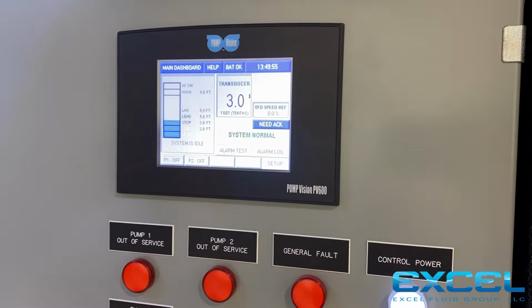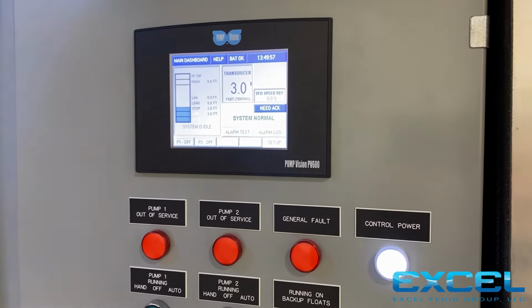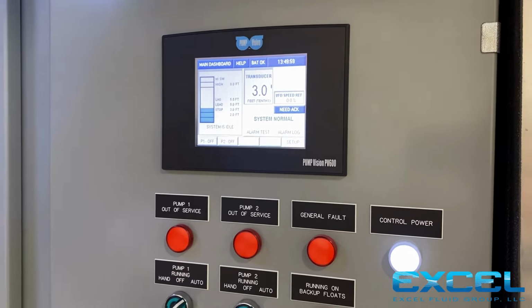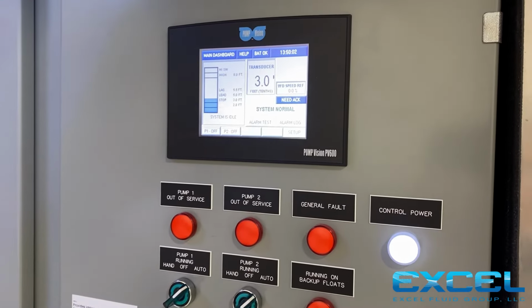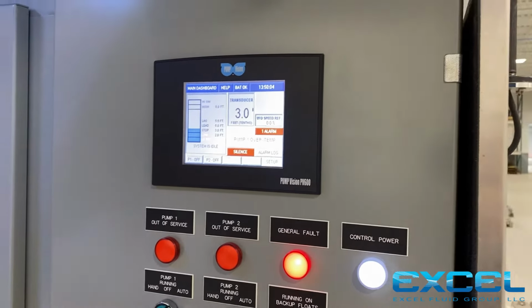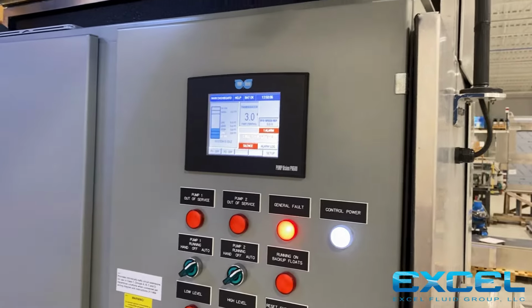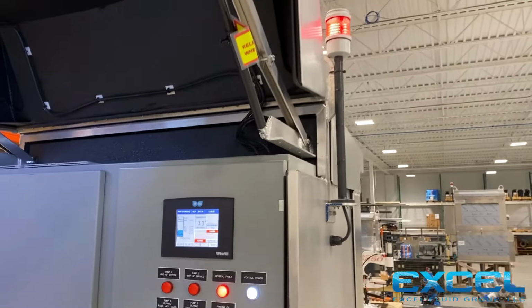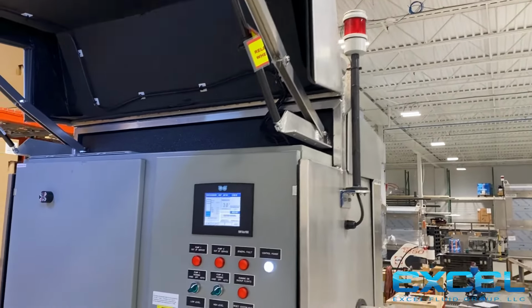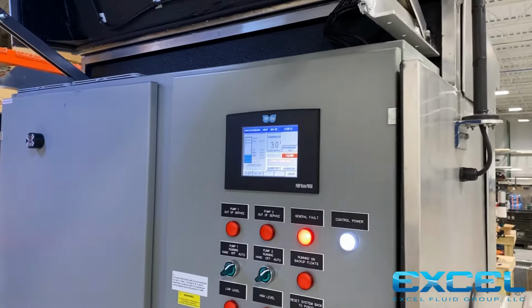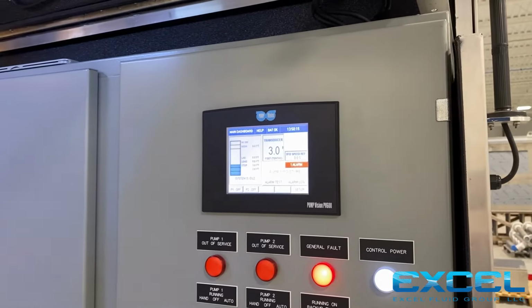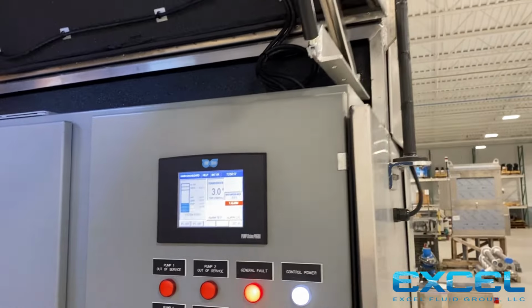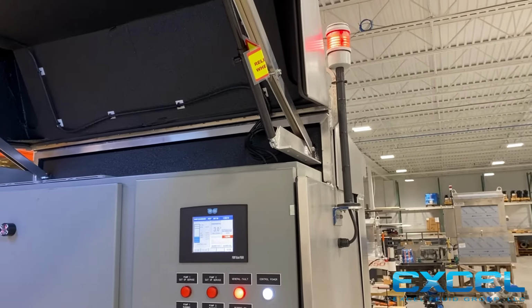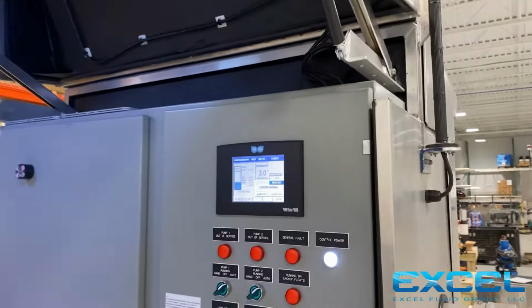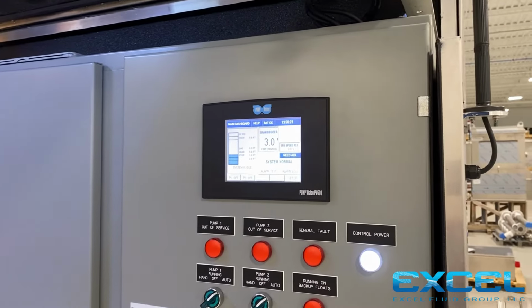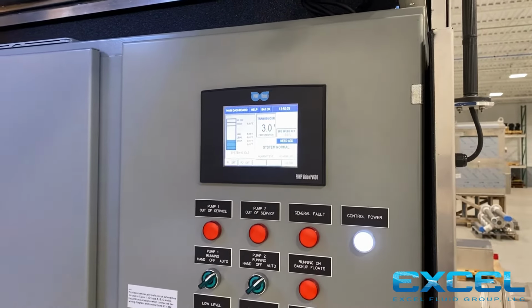If it's hooked up to telemetry or SCADA, this is all going to be communicated to you. We can also simulate an overtemp, and that's where we're going to be sending both an audible and a visual alarm there. We can also simulate seal fail. Seal fail is going to call an alarm and also illuminate the exterior light, so even on a drive-by, you're going to be able to see something's going on with my pump station. We're back to the normal operation here, and I'll take you inside.